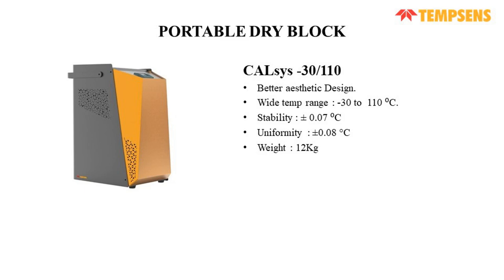All these dry block calibrators come with inserts, and the inserts have holes according to the customer's needs. Two holes will be 6.5 mm, and two will be 8.5 mm. And if you have any customizable RTDs or thermocouples, we can customize the block also. So the holes will be according to the customer's need.